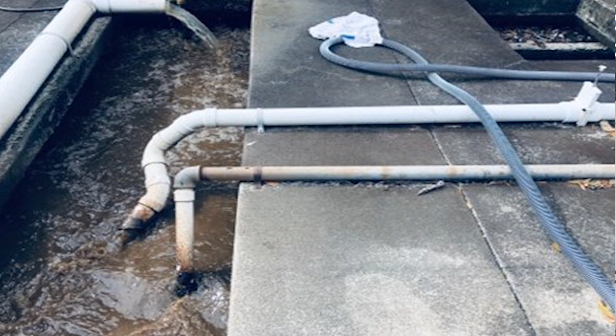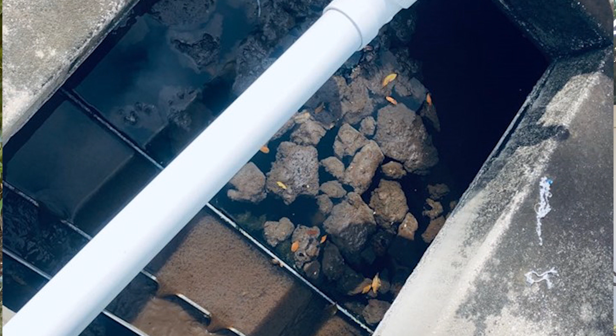First, since the meter relies on particles or bubbles flowing in the liquid, the lower limits for concentrations and sizes of solids and bubbles in the liquid stream must be considered. Second, the liquid must flow at a rate high enough to keep the particles suspended. Lastly, to obtain an accurate flow rate, ultrasonic flow meters require that the pipe flow full. Now let's take a look at the demonstration of the technology.